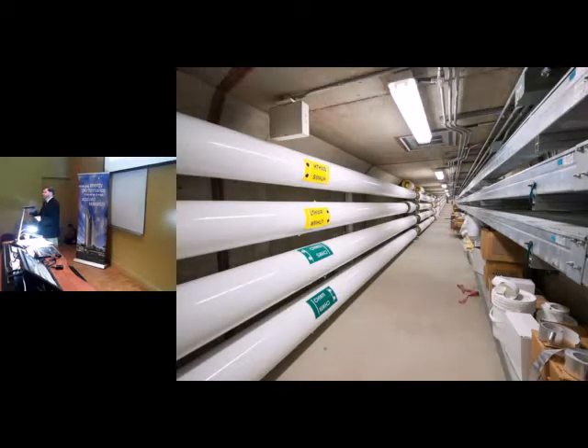So the water entering is at 180 degrees, the water leaving is at 150 degrees. We then take that medium temperature water and push it through the air handlers. So we then heat all the outside air with that medium temperature water. We drop that water temperature down from 150 degrees Fahrenheit down to 100 degrees Fahrenheit. And we'll talk about why we do that in a moment or two. So what we do is we take the very, very hot water, rather than sending it back to the boilers at the powerhouse at a low temperature, we get it down to a very, very low temperature. And that allows us to do a couple of interesting things.